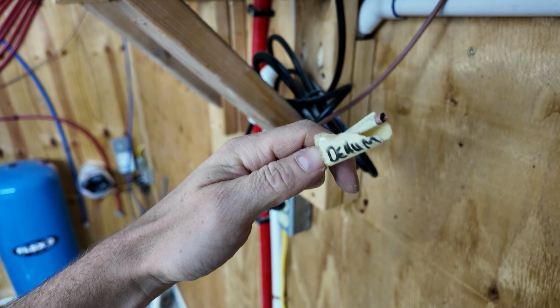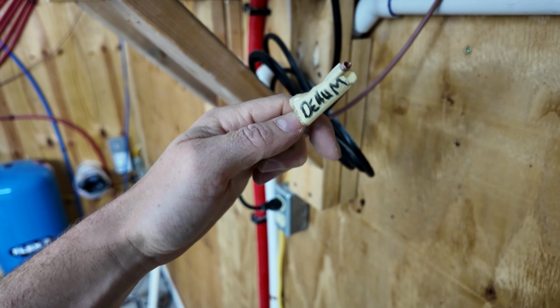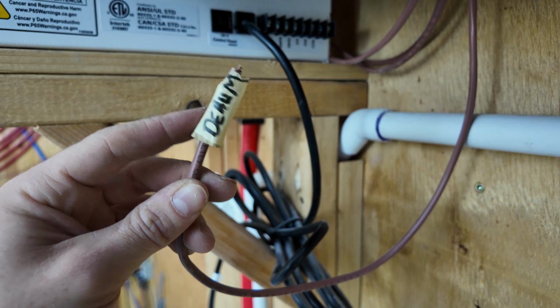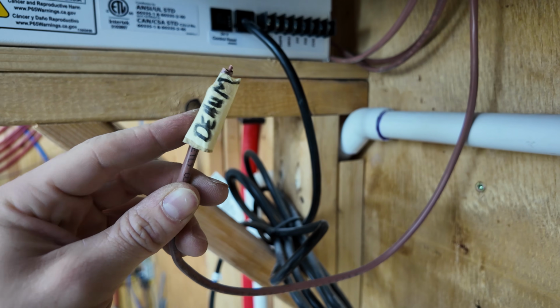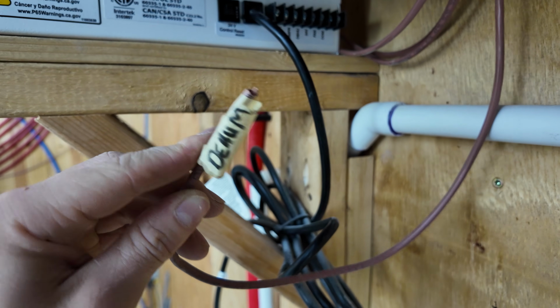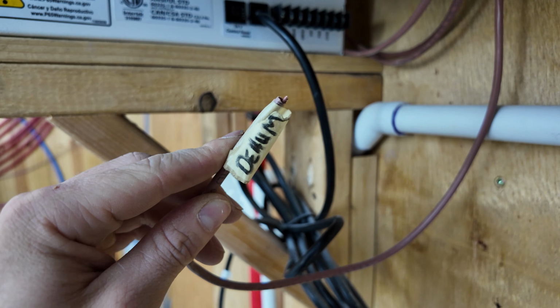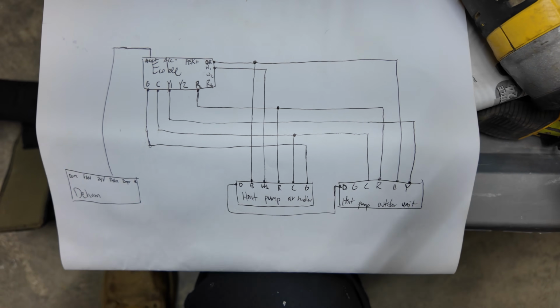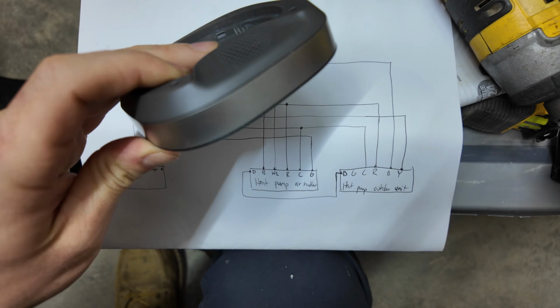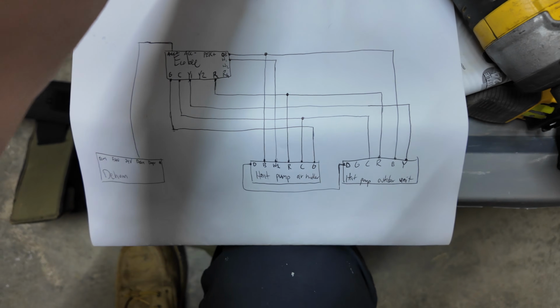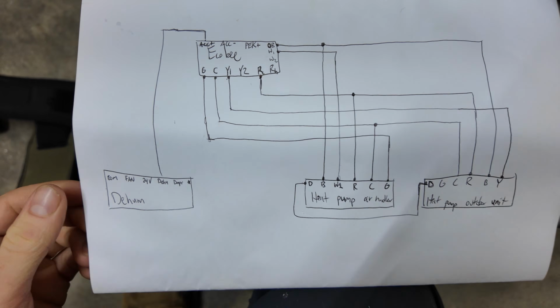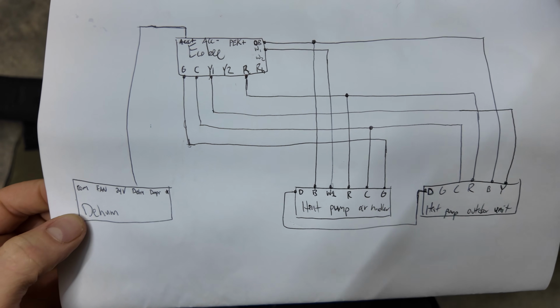I'm going to go ahead and wire up the low voltage while I'm at it as well. It's 24 volt controls, and this thermostat wire runs to the same location as our main thermostat, so that's going to be wired in parallel with our main HVAC up there. I did some manual reading of our nice little ecobee thermostat to figure out the best way to wire this up, because it does support an accessory, in our case a dehumidifier.